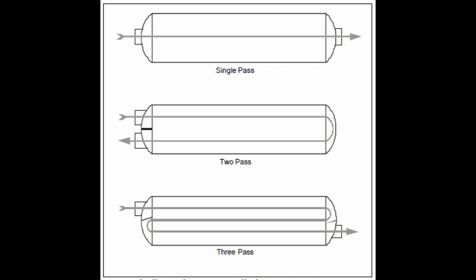As shown in the picture, a one pass heat exchanger, also known as a single pass heat exchanger, has the fluid — either the refrigerant or the chilled water — flow through the tube once and then out of the heat exchanger. This design is typically used in smaller chiller systems with lower heat transfer requirements.